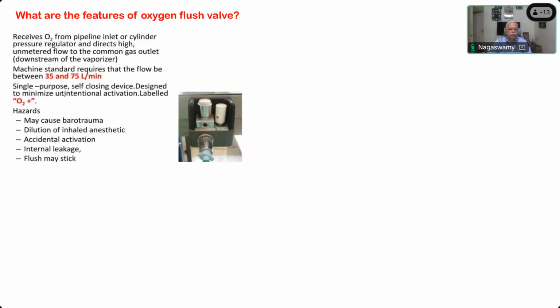It is a single purpose self-closing device designed to minimize unintentional activation, labeled oxygen plus. That is the symbol that is given. The hazards: it may cause barotrauma because it is delivered at 45 psi and not 14 to 15 like you get from the flow meter. Dilution of inhaled anesthetic gases can happen. Accidental activation can make a tight bag. This is the oxygen flush here.